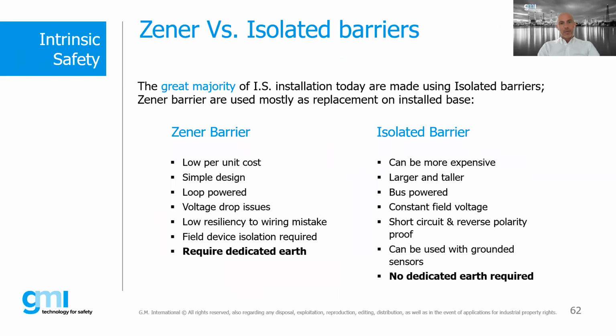The last slide is regarding Zener barriers. We have talked about Zener and isolated barriers, and if you look at the features, we see that the Zener barrier has lower cost, a very simple design, is completely loop powered, has some voltage drop issues, and, most important, must be used with isolated field devices. So the devices must be isolated, cannot be uninsulated, and it also requires a dedicated earth connection.